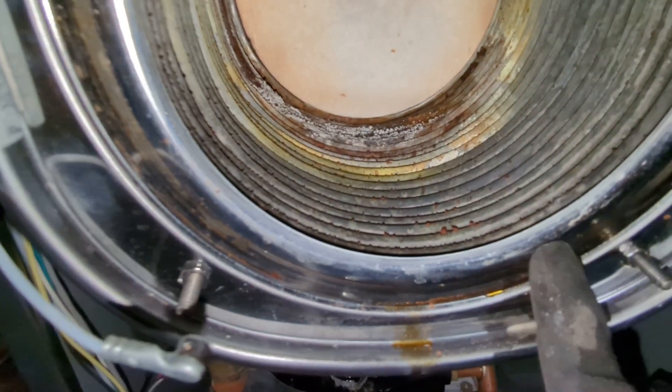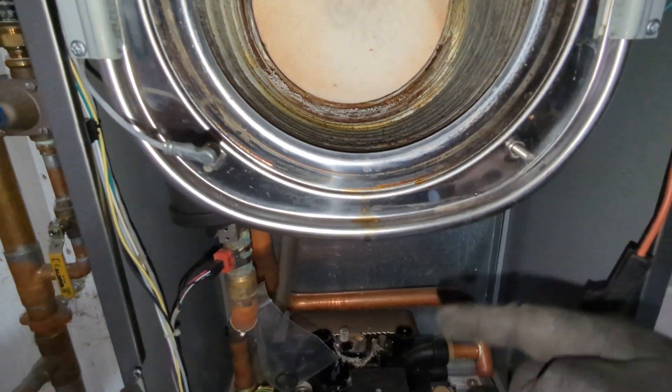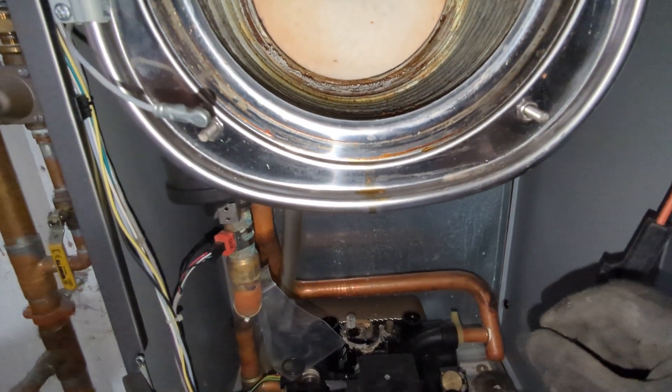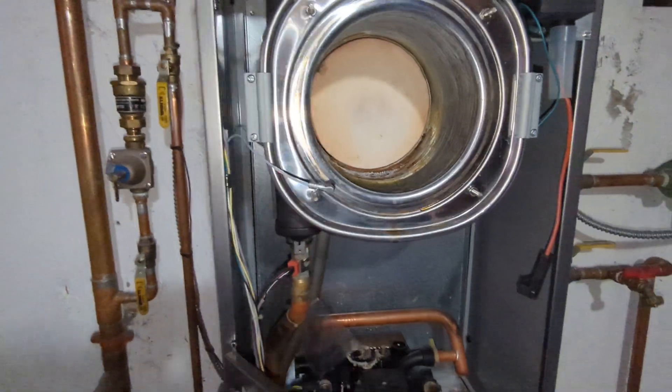They all leak at that same spot right up there, right where that coil dips into the heat exchanger. They eventually leak out the front and leak down the burner tube into the gas valve, puddling on top of it. The gas pressure can't overcome the weight of the water, and it leads to a lockout — no ignition.